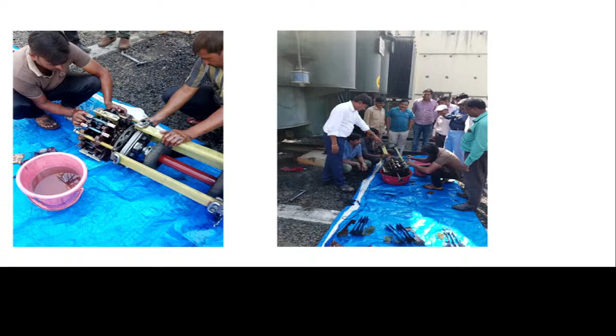Secondly, the air cell. On field, people are only told that there is an air cell in this. So this type of air cell we are providing, to avoid direct contamination with the atmospheric air. The precaution, every time what I am seeing is that the substation in charge thinks that if I fill more oil, I will not have trouble in future, 2 drums extra. But particularly for the air cell conservator, I want to tell all of you that you have to fill only 1/3 of oil in the air cell conservator.